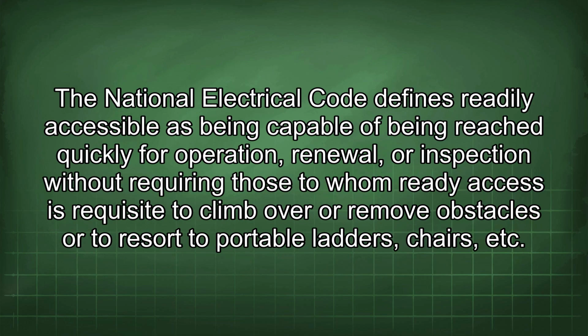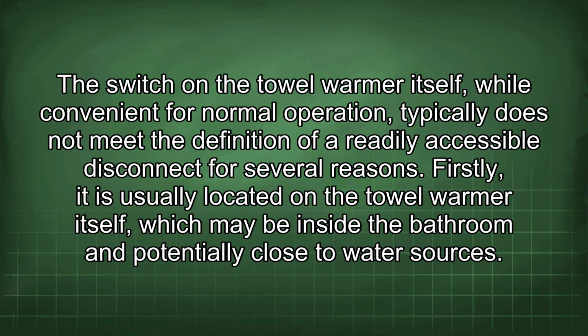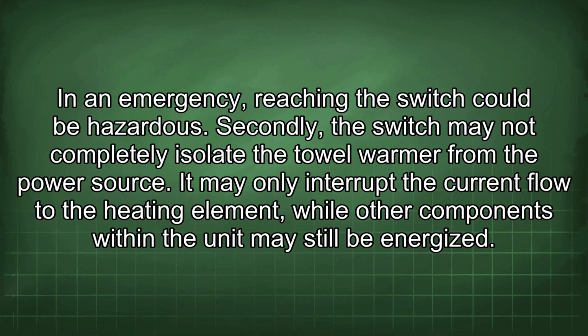The National Electrical Code defines readily accessible as being capable of being reached quickly for operation, renewal, or inspection without requiring those to whom ready access is requisite to climb over or remove obstacles or to resort to portable ladders, chairs, etc. The switch on the towel warmer itself, while convenient for normal operation, typically does not meet the definition of a readily accessible disconnect for several reasons. Firstly, it is usually located on the towel warmer itself, which may be inside the bathroom and potentially close to water sources. In an emergency, reaching the switch could be hazardous.